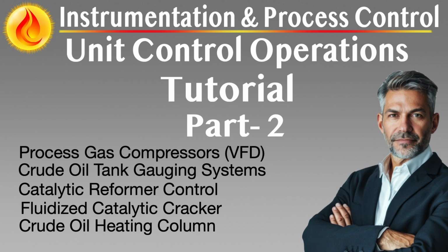The heating column's role in heat integration further enhances its operational complexity. It interacts directly with the crude preheat train, where heat recovery from overhead vapors or bottom stream is used to pre-warm incoming feed. Advanced control strategies synchronize column heat duties with hot oil circulation loops, furnace firing rate, and main CDU heat exchangers to achieve maximum thermal efficiency. APC logic may optimize firing rate, steam stripping, and exchanger bypass based on calculated pinch points or real-time energy KPIs.